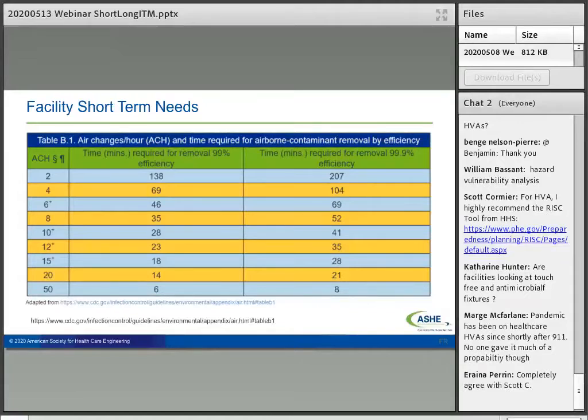Table B1: the CDC recommended air exchange and time required for airborne contaminant removal by efficiency. On the left, if you have 8 air exchanges and you're looking for 99% removal efficiency, you'd be looking at 35 minutes before you should enter that space. For 99.9%, it would be 52 minutes. So you'd use this chart to find the air exchanges for your space and then the time required for removal.